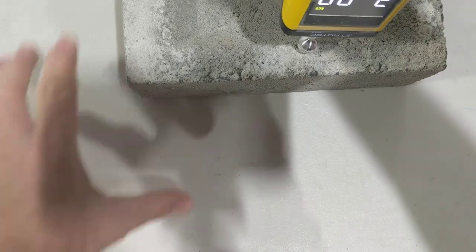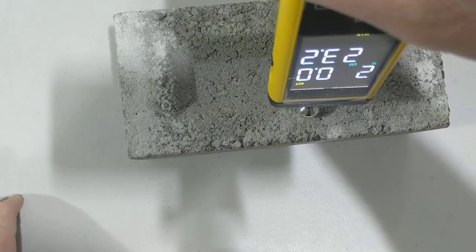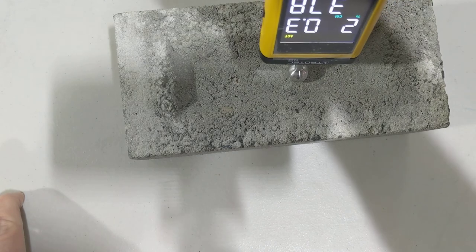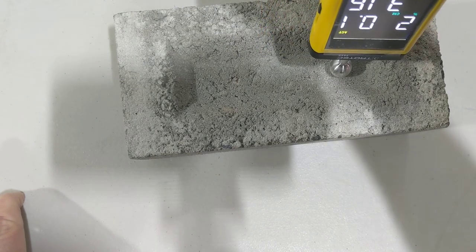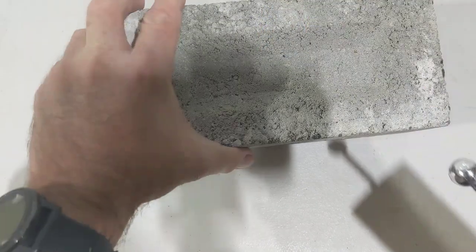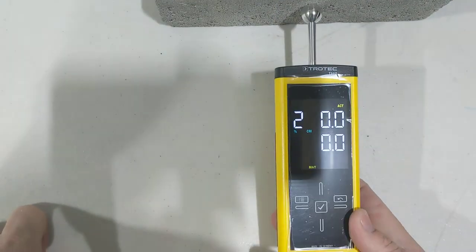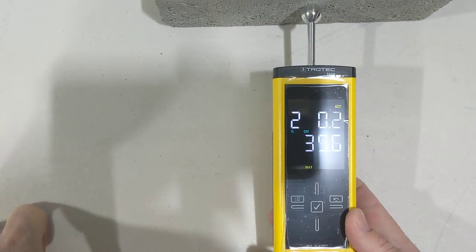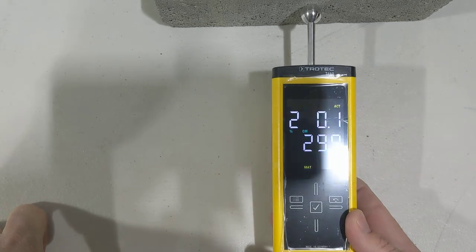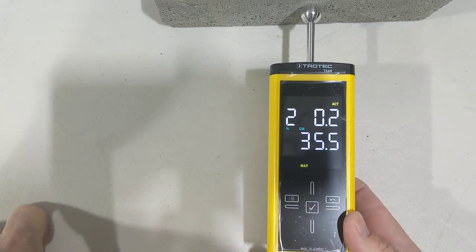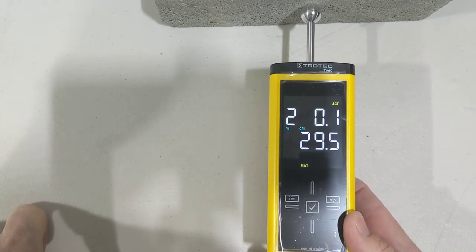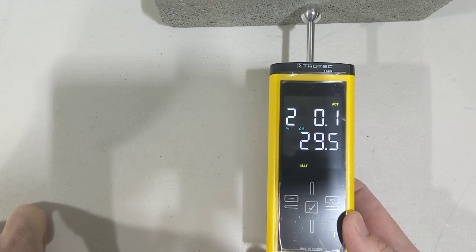I'll show you a number here. We're pretty dry. That top number is 0.2—it's not even reading; it's really dry, a dry concrete block. The top number you want to read under two.